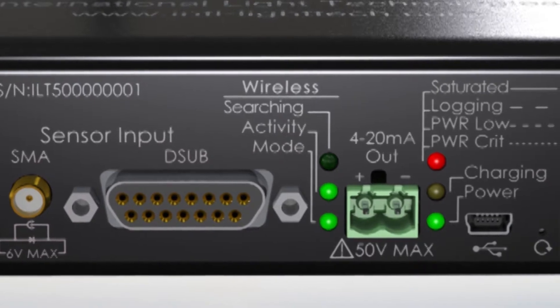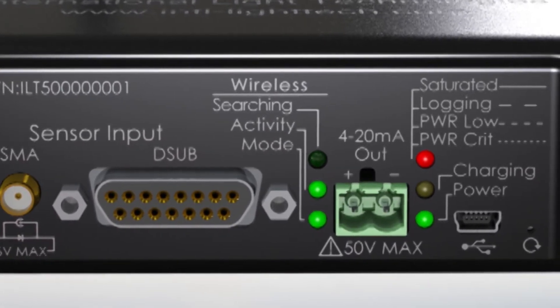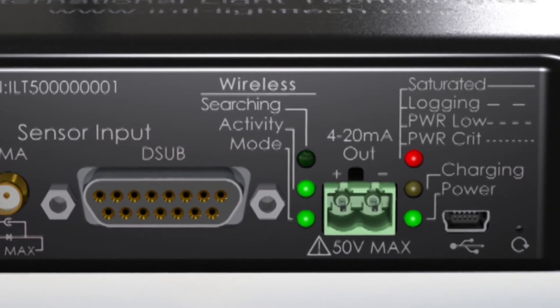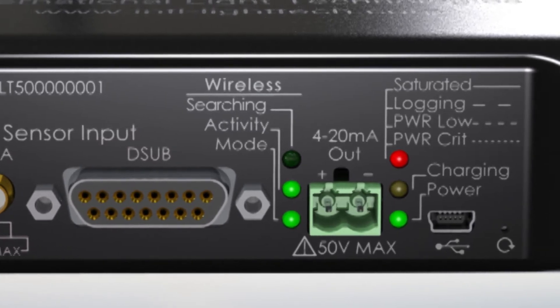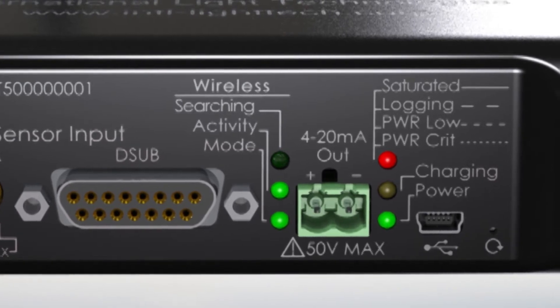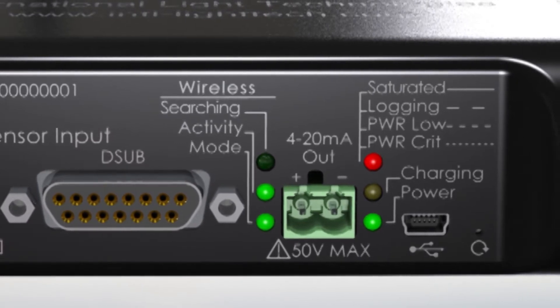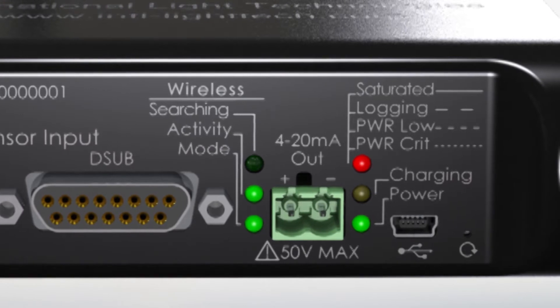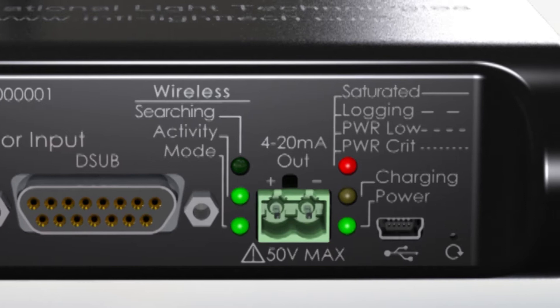The standard 15-pin D-sub connector ensures backwards compatibility with all new and existing ILT sensors, filters, optics and our NIST traceable ISO 17025 accredited calibration. The wireless LEDs indicate the status of the wireless connection and data transfer. A 4 to 20 milliamp jack allows the data to be used for process control via connection to a PLC.